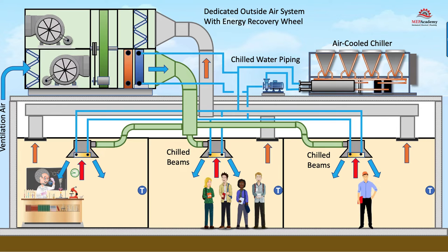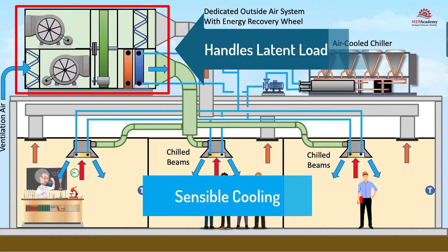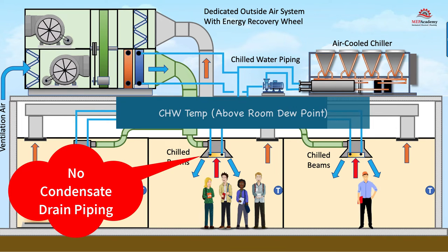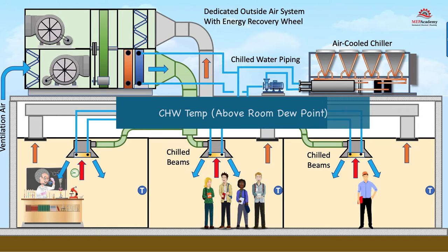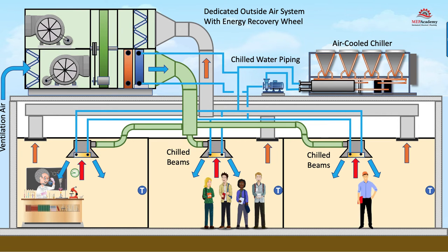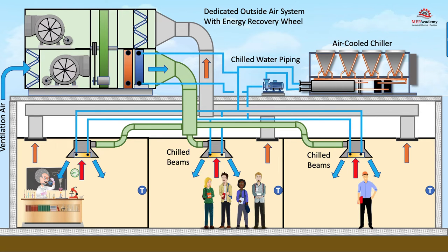The chilled beams are designed to handle sensible load, while leaving ventilation and latent load requirements to the main DOAS or AHU. This eliminates the need for condensate drain piping at each chilled beam, as the coil temperature will be maintained above the dew point temperature. The AHU unit can be sized just to handle the ventilation requirements, allowing for a smaller than normal unit. However, it is imperative that the AHU be sized to handle the dehumidification requirements, as the chilled beams handle strictly sensible cooling. The primary air must be dry enough to handle any space latent load while maintaining the indoor dew point low enough to prevent condensation on the chilled beam coil.